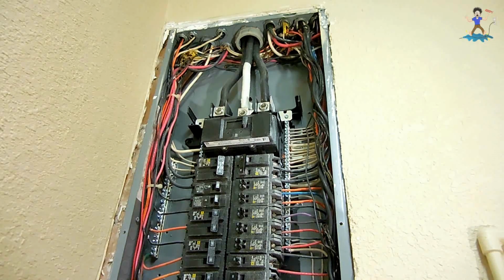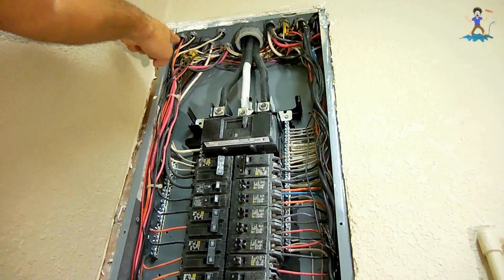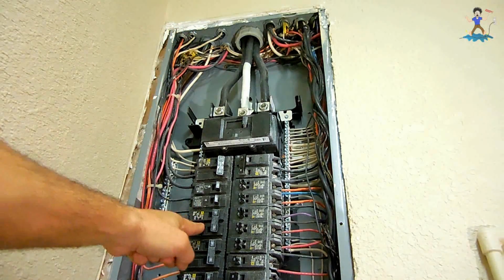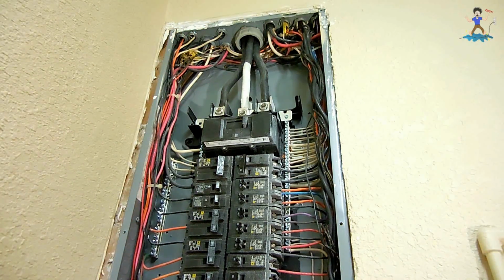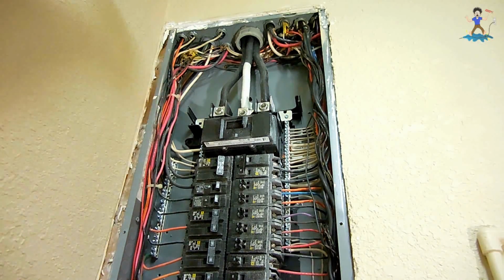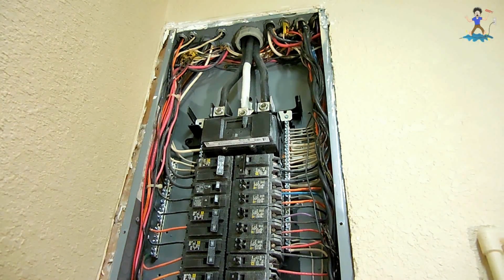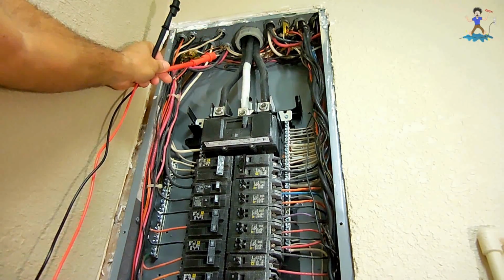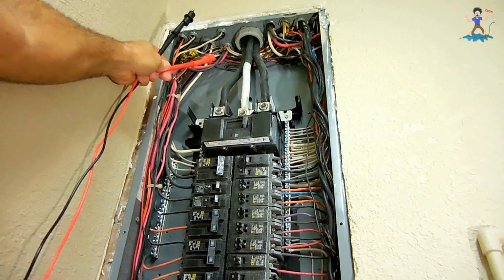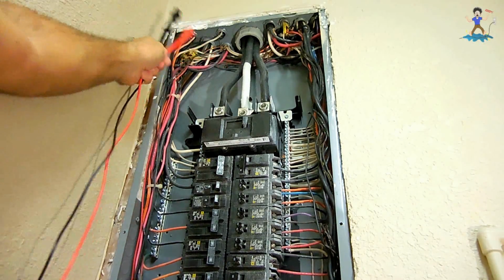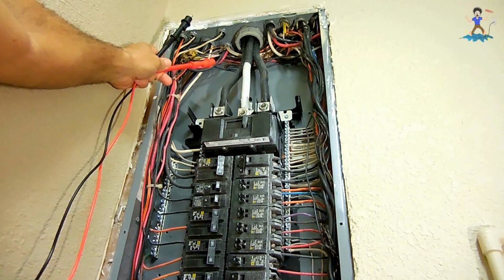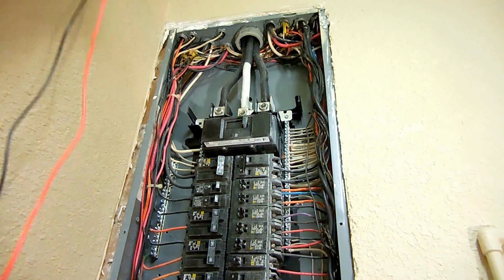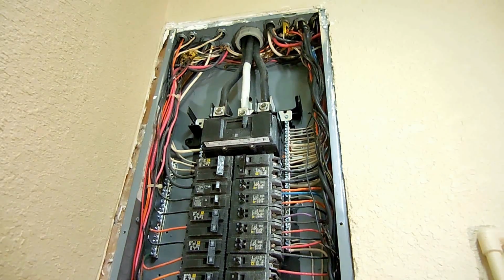Once that test is complete, then you're going to disconnect the wires inside the conduit that are already there, which may be connected to a breaker. You're also going to disconnect the wires at the other end away from the panel where you pulled the red wire into the panel from. So when both ends are exposed, you're going to take the Megger and take a reading between the red wire you just pulled in and the black wire that you see here. You're going to take another reading between the red wire and the white wire you see here. Make sure the readings are all high. If they are, then everything's okay and you're good to go.